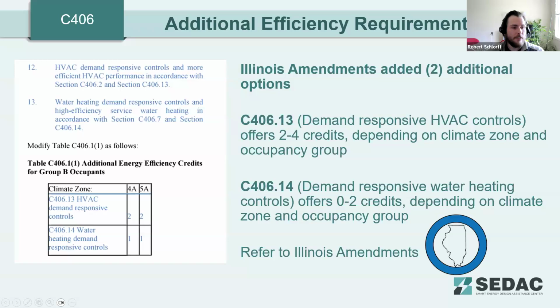One more quick addition to the additional efficiency measures here is that the adopted Illinois amendments did add 2 additional options to this list. So these are C406.13, demand responsive HVAC controls. So essentially HVAC controls that have some connection to the grid and are able to respond and react to signals from the overall energy grid in terms of managing their load. And then similarly, C406.14, demand responsive water heating controls. So both of these, the C406.13 offers about 2 to 4 credits, depending on the climate zone and occupancy group.